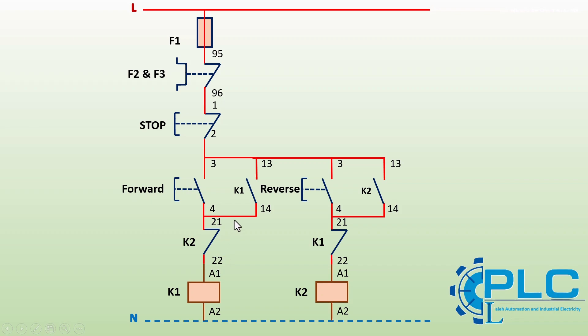In the second part of this circuit, which controls the motor's reverse rotation, the reverse start push button and its holding auxiliary contact are connected to the input of the normally closed auxiliary contact of the forward contactor. The output of this normally closed contact is then connected to the coil of the reverse contactor. This contact also acts as an interlock, ensuring that whenever the forward contactor is active, the reverse contactor cannot be energized. This prevents short circuits and ensures safe operation.